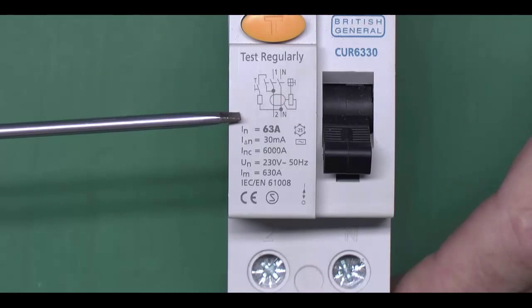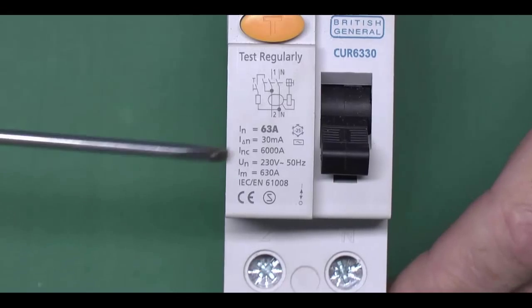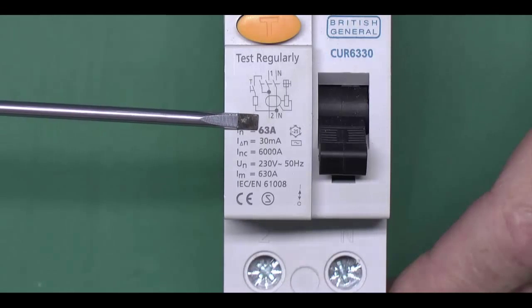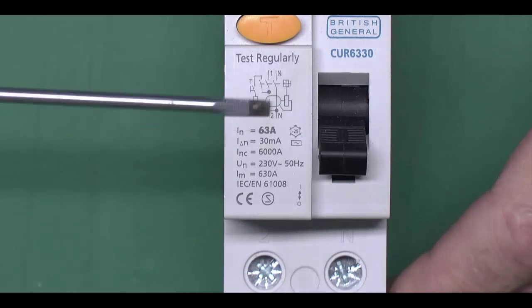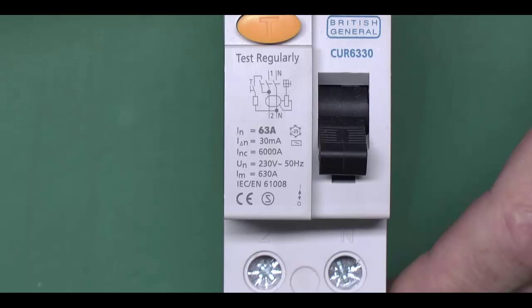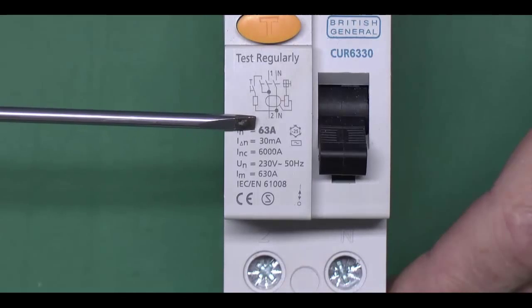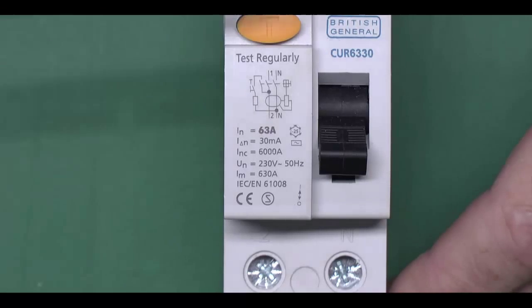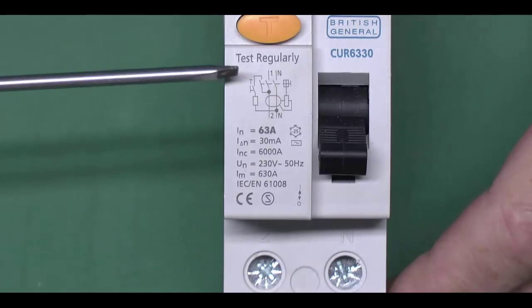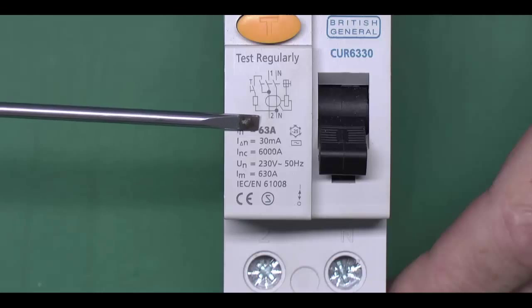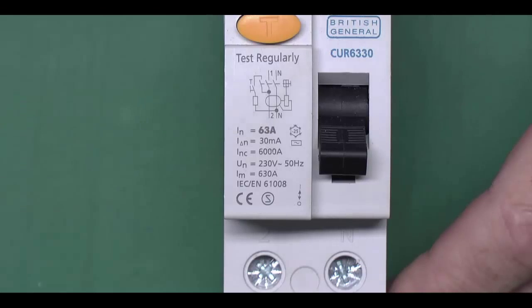Now it's important to note that these devices do not react to overloads or short circuits. Most of them will have a rating on the front here, in this case 63 amps, but that's just a rating of the internal contacts and switching mechanism. That does not mean it's going to suddenly trip out when you exceed 63 amps. You could put 200 amps through this device, it won't trip or do anything. Again, if you shorted out the supply and several thousand amps flow through it, again, it's not going to disconnect at all. That's purely there as a maximum rating of equipment you can connect downstream of it.